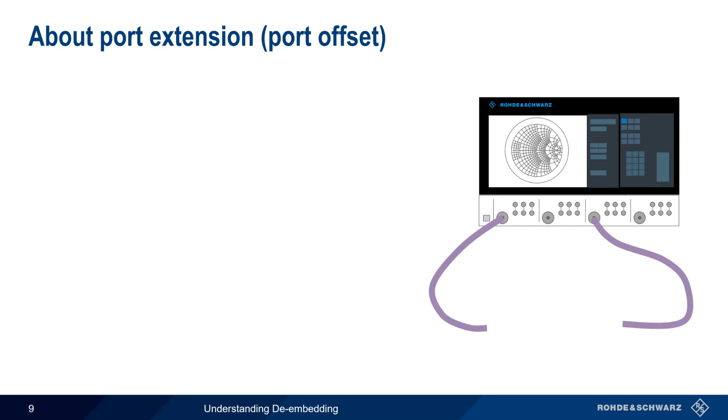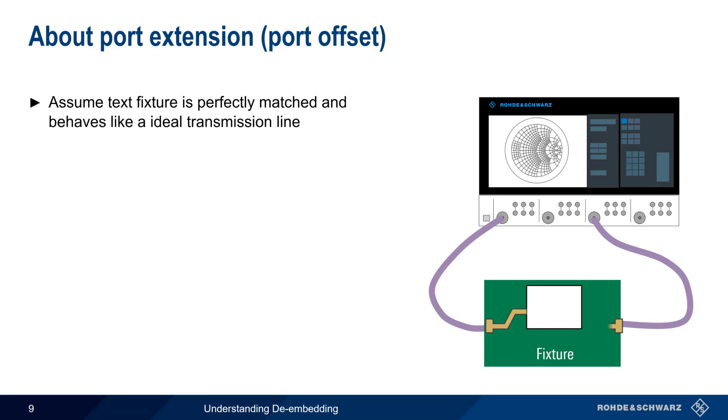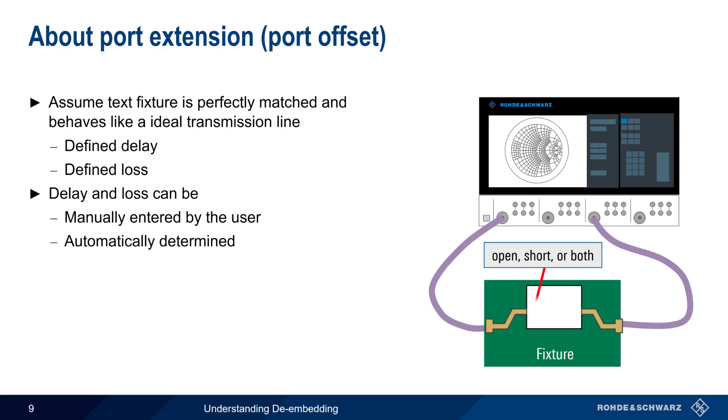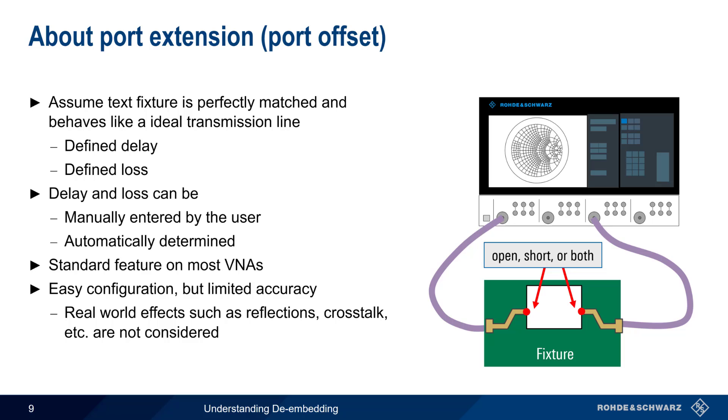We'll start with something called port extension, or port offset. The reason this methodology is called port extension is that we assume the test fixture is perfectly matched, and that it behaves like an ideal transmission line. The fixture is treated like an extension of the VNA cable, with a defined delay and a defined amount of loss. The amount of delay and loss introduced by these extensions may be manually entered by the user, or they may be automatically measured and determined by the VNA. This is done by placing an open, short, or both at the connection points. Port extension is a standard feature on most VNAs. It's relatively easy to configure, but accuracy is somewhat limited due to the fact that real-world effects like reflections, crosstalk, etc. are not considered in this methodology.